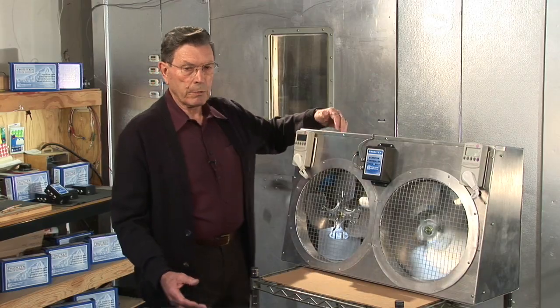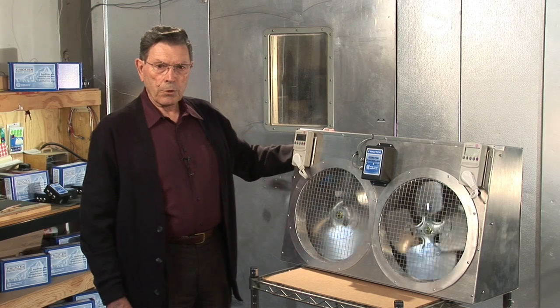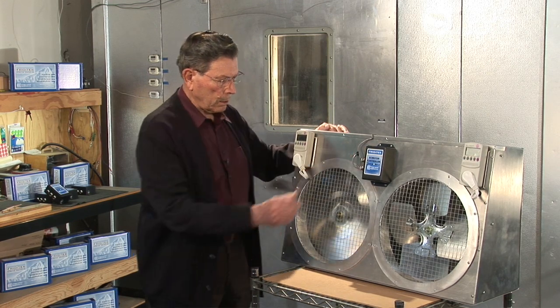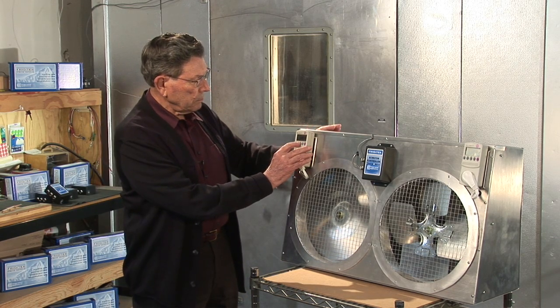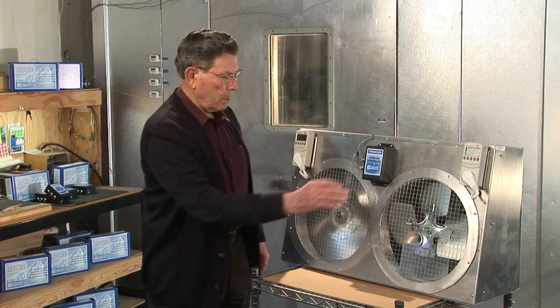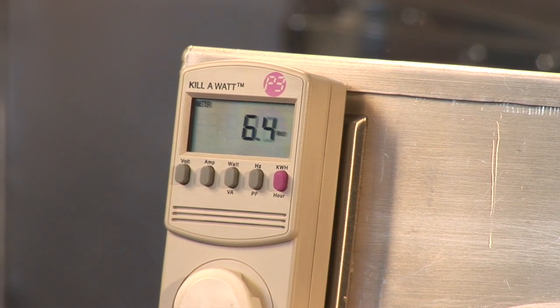Recognize that motor would be running 24 hours a day. Whereas with this EC motor, you'll see that it will draw about half as much energy at high speed — right now it's reading 75 watts. And at low speed, as it settles down, it will draw only 5 to 6 watts — under 6 watts. That's a tremendous amount of savings.